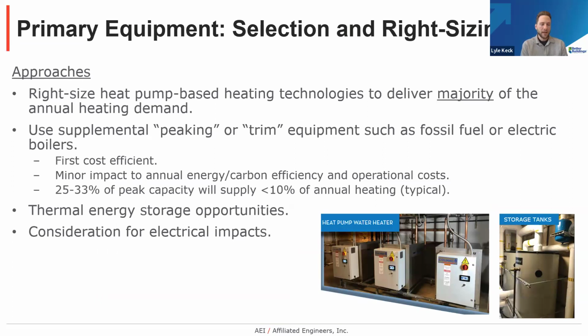So one approach is to right-size the heat pump-based or heat recovery-based heating technologies to deliver a majority of the annual heating demand, not necessarily all or 100%, but try to get the biggest area under the curve, if you will. Using supplemental peaking or trim devices, such as fossil fuel or electric boilers, is a really good way to make it first cost efficient and develop a practical and efficient solution. And oftentimes you'll see diminishing returns, or exponential needs, to get from, let's say, a 90% carbon savings all the way to 100% carbon or full electrification. So applying a supplemental device for peak or trim heating is very important. And usually it has a very minor impact on the annual energy and carbon efficiency or the operational costs if you're only using it under this mode of operation.